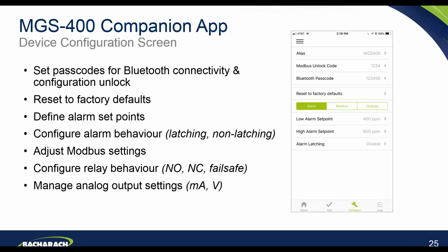On the device configuration screen, this is where you will set your passcodes for the Bluetooth connectivity and configuration lock. You can reset the instrument to the factory defaults. You can define your alarm set points on here. Again, if you see the image on the right there, if you just touch the alarm, the low alarm set point for example, it will bring up a small box and you just type in the alarm set point you want to have for that.